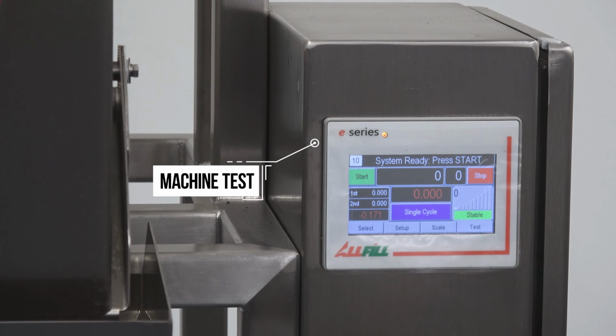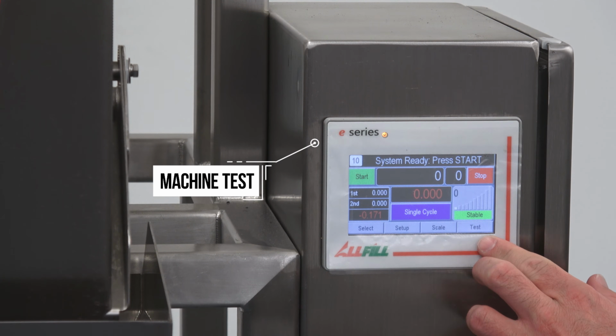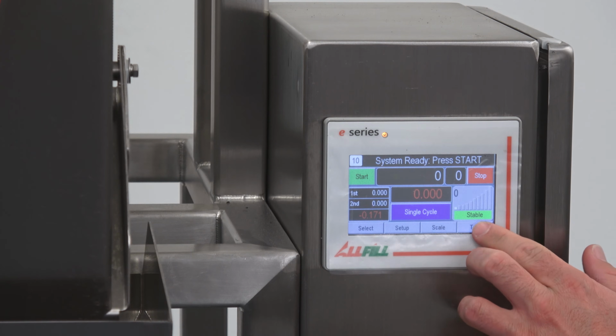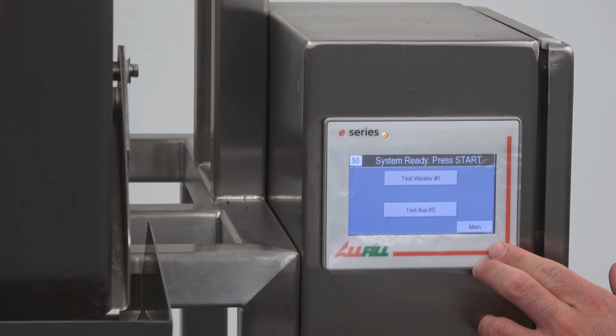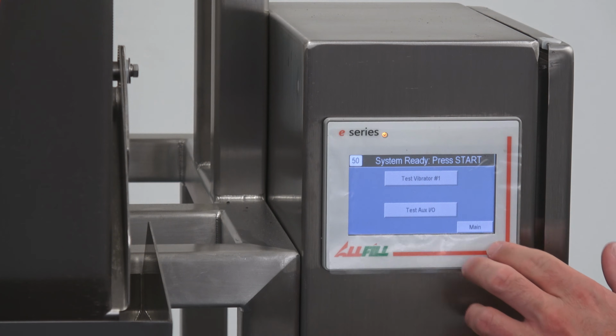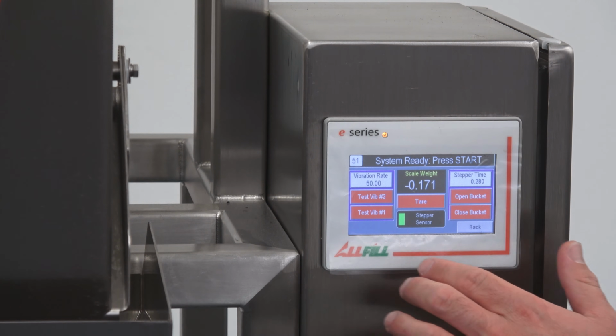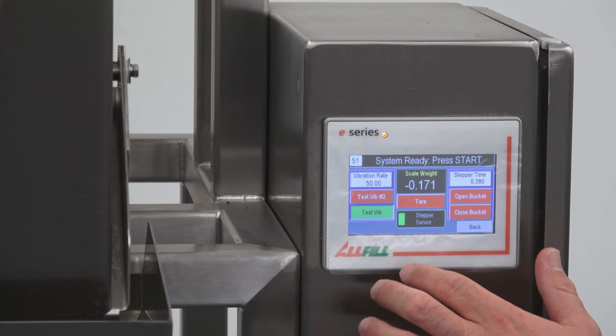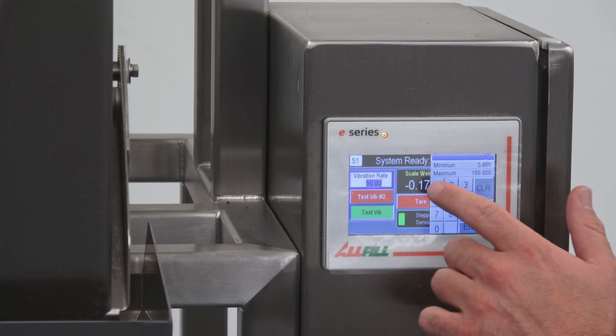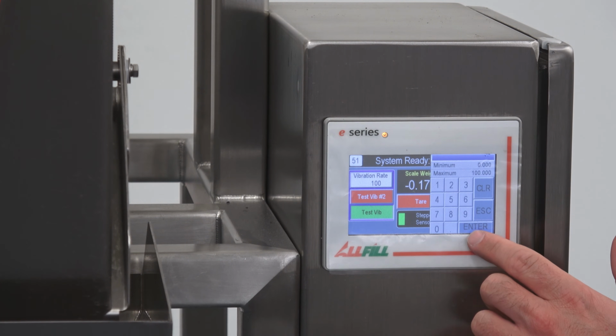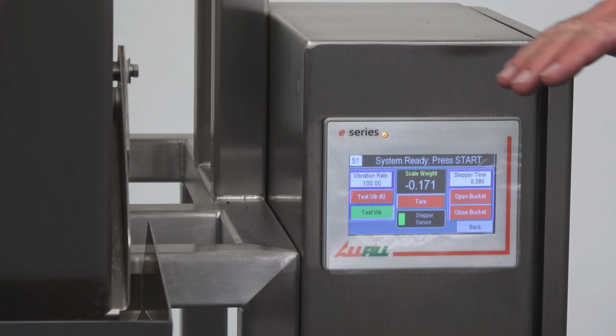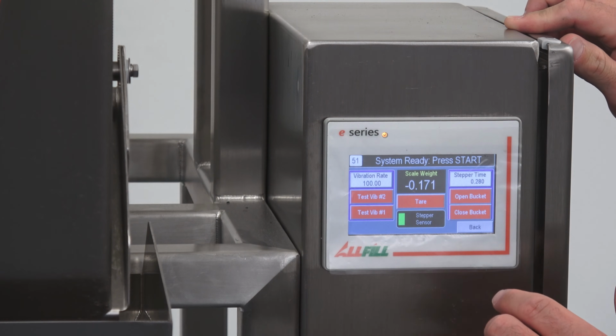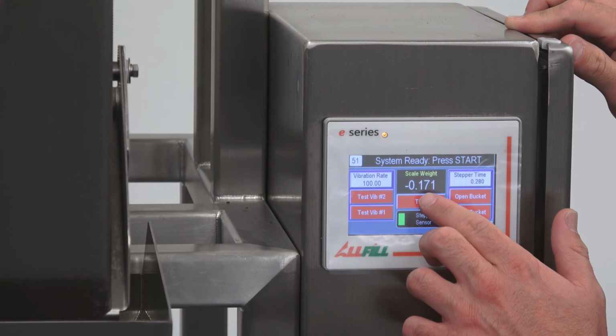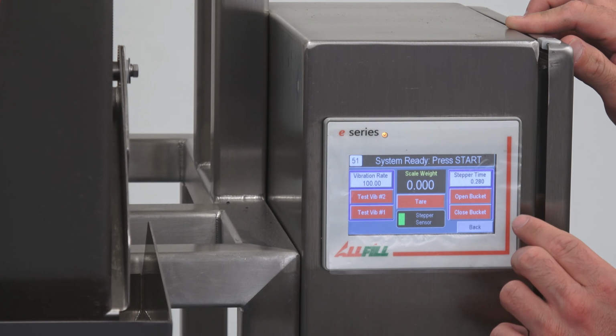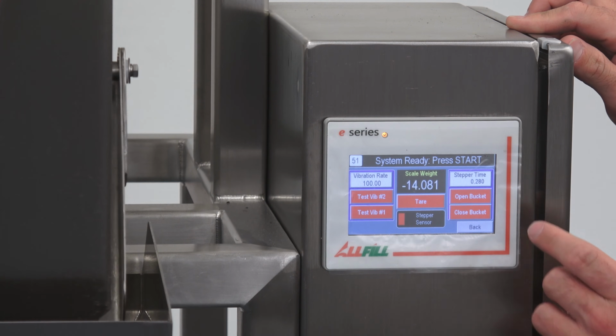Now that we have the scale calibrated, we can test the functionality of the machine in the test menu down here in the bottom right. The first button is test vibrator number 1, and this machine only has 1 vibrator. We can test vibe 1. Right now it's at 50%. I can turn it up to 100%. Hit enter. You'll hear the vibration increase, and you can feel it on the pan as well. I'm going to turn off the vibrator. In the middle here, I can tare the scale. We can also test the bucket to make sure it opens and closes properly.